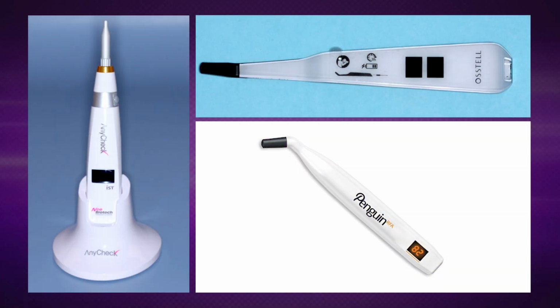Tim, do either of these concepts evaluate osseointegration? No, they don't. These are adjunctive devices. There's really no true way to evaluate osseointegration. However, these add a degree of analytical value to your analysis of the stability of the implant. You use these in addition to x-rays, in addition to physical tapping with the handle of an instrument, and your visual inspection, but these give a quantitative analysis which can certainly increase your assurance that the implant is ready for restoration.